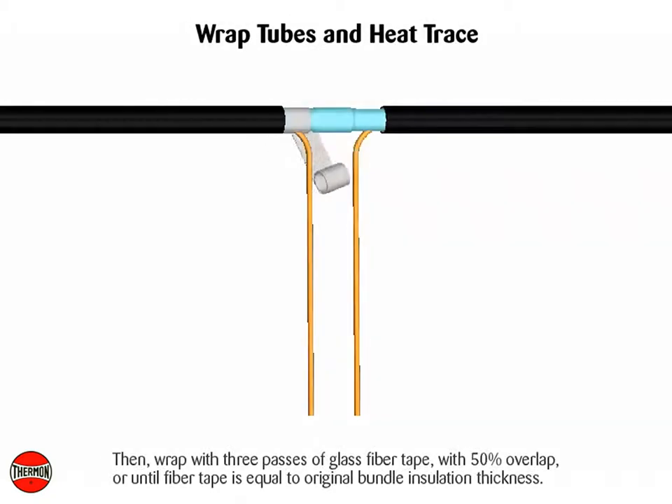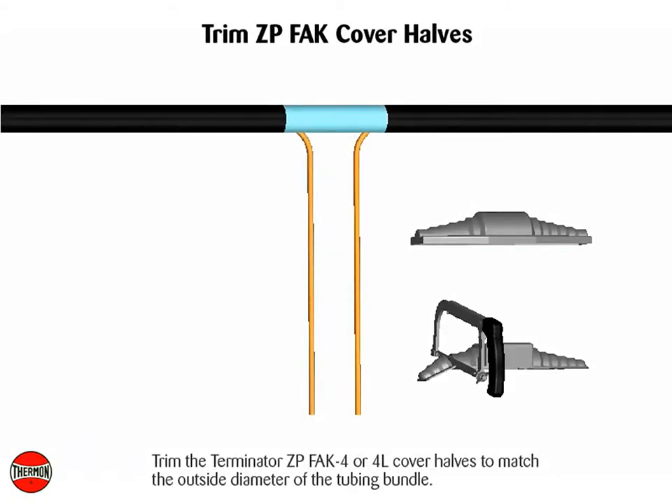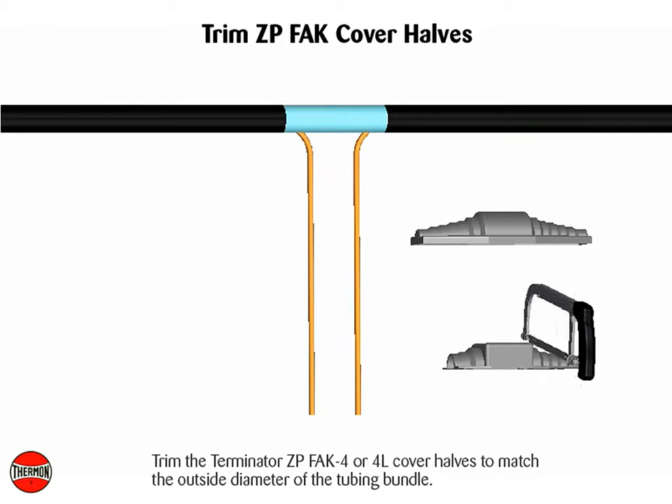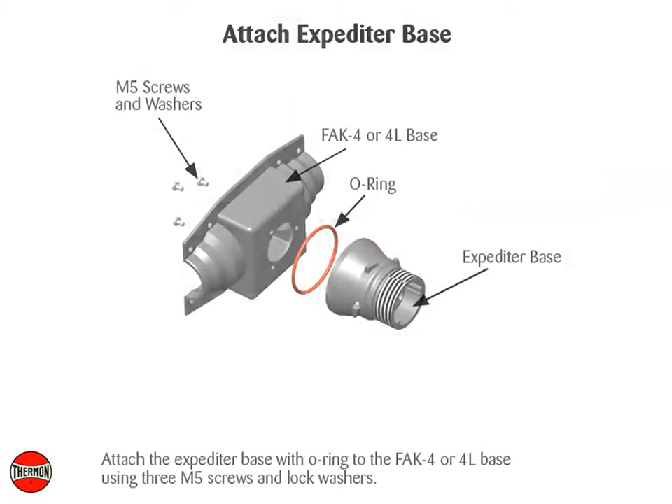Then wrap with 3 passes of glass fiber tape with 50% overlap, or until fiber tape is equal to original bundle insulation thickness. Complete with 1 additional pass of heat reflective tape. Trim the Terminator ZP-FAK4, or 4L cover halves, to match the outside diameter of the tubing bundle. Attach the expediter base with O-ring to the FAK4, or 4L base, using three M5 screws and lock washers.